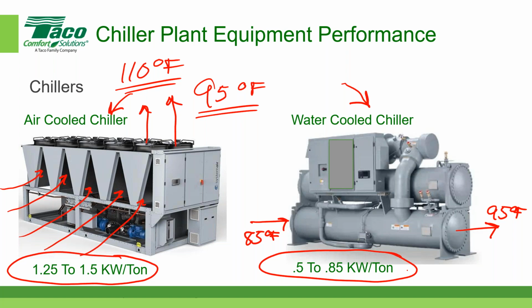There's a couple of questions associated with energy. When you're talking about kilowatts per TR for water-cooled chillers, someone is suggesting you should add the fan power and pump power in order to see the real numbers. Well, that's a very good point. These numbers represent, on the water-cooled side, just the chiller. We're going to add the loads of the other components, the cooling towers and the pumps, so you can get a picture of the total kW per ton. But most of the time, we think of packaged air-cooled chillers as the total power, and we think of water-cooled chillers as a standalone component. But you're right, you would add the power of the pumps and the cooling towers to get a full plant picture of what's going on.